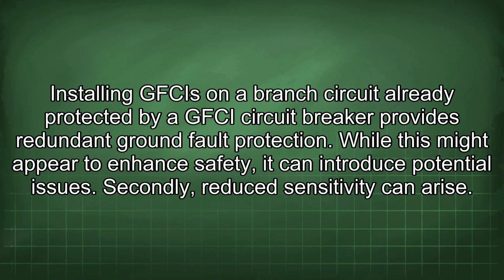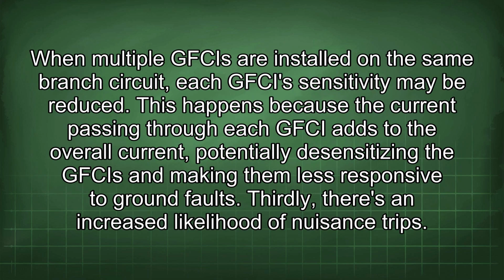Secondly, reduced sensitivity can arise. When multiple GFCIs are installed on the same branch circuit, each GFCI's sensitivity may be reduced. This happens because the current passing through each GFCI adds to the overall current, potentially desensitizing the GFCIs and making them less responsive to ground faults. Thirdly, there is an increased likelihood of nuisance trips.